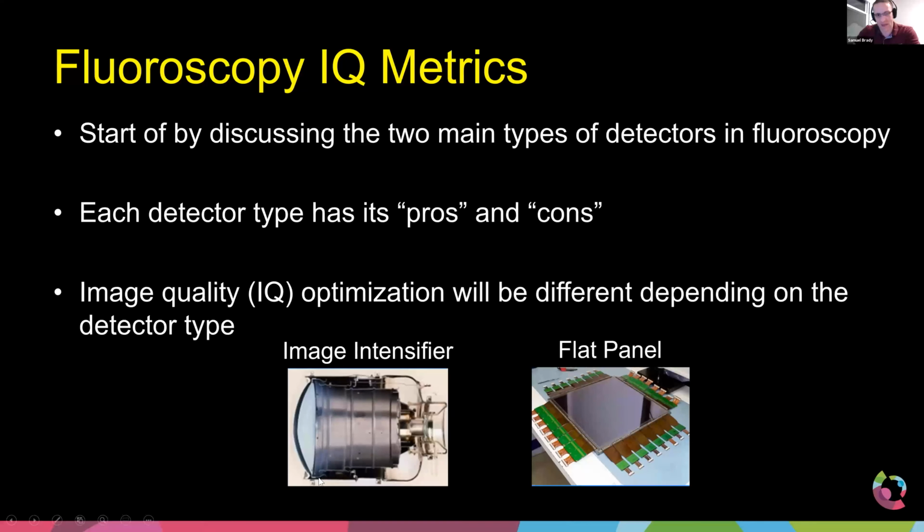It's basically a vacuum tube. It's a big empty hollow system. It's got your indirect crystals on top, usually cesium iodide. So when the X-rays come in, they strike the cesium iodide, they get turned into light. That light gets turned into electrons.